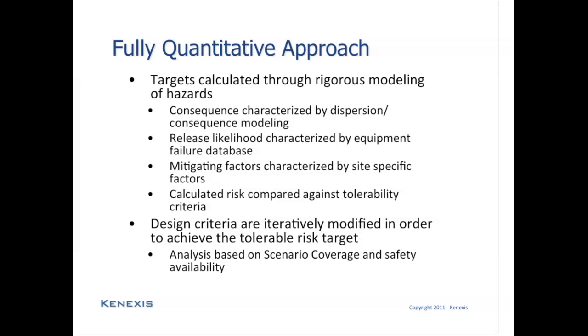And instead of trying to calculate how frequently a release will occur based on a set of known initiating events, we are going to instead do a statistical probabilistic technique that will infer the rates of loss of containment based on the quantity and type of equipment that is contained within a zone, and use historical analysis, statistics based on the history of these types of processing equipment to determine their leak rates, and also to statistically determine the distribution of the sizes of the leaks that have occurred. So we're not going to try to predict based on initiating events. Instead, we're going to look at statistically how often have leaks occurred in this type of processing equipment in the past, and use that as a basis for calculating how frequently we expect these leaks to occur in the future.